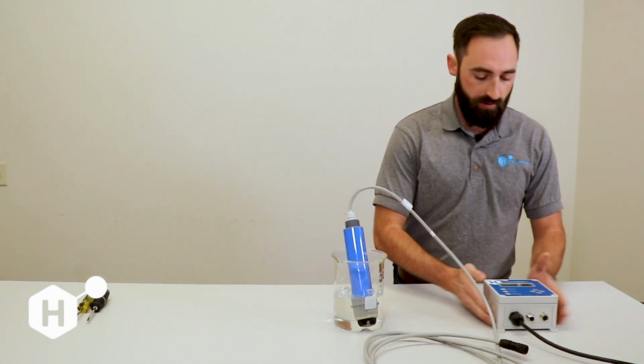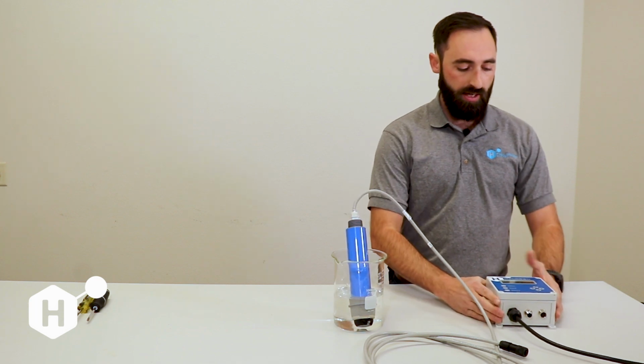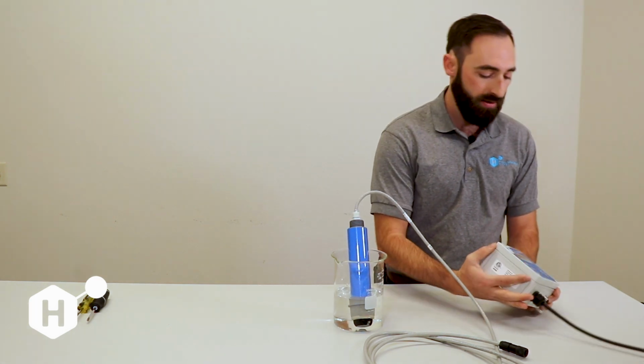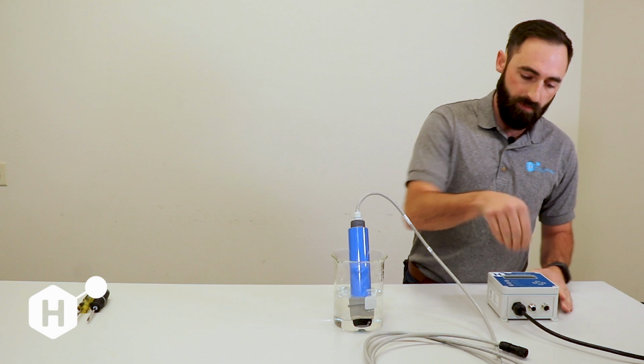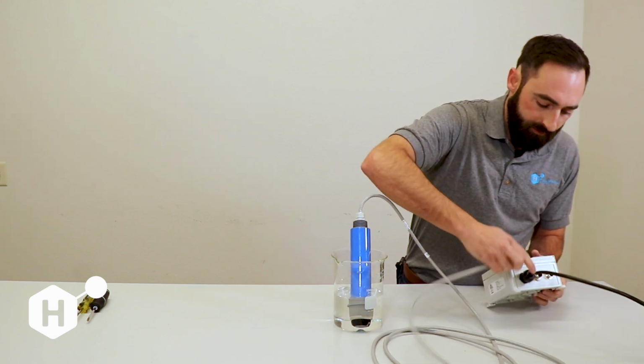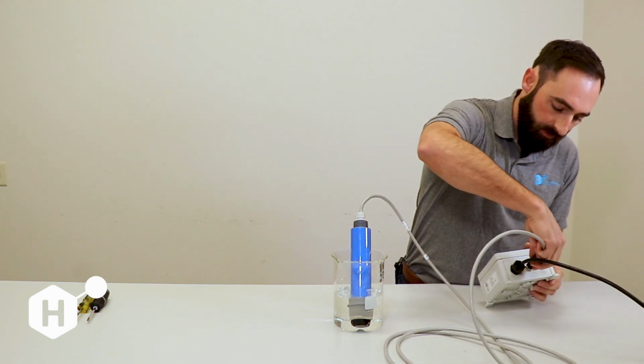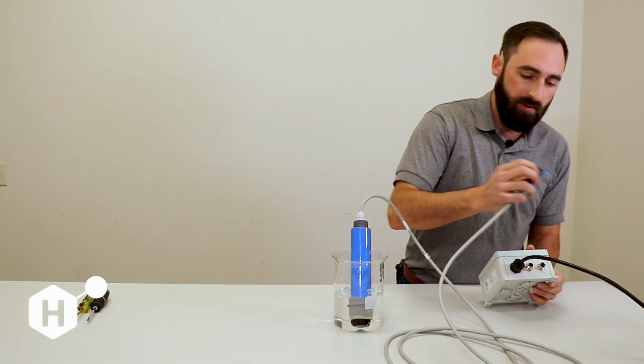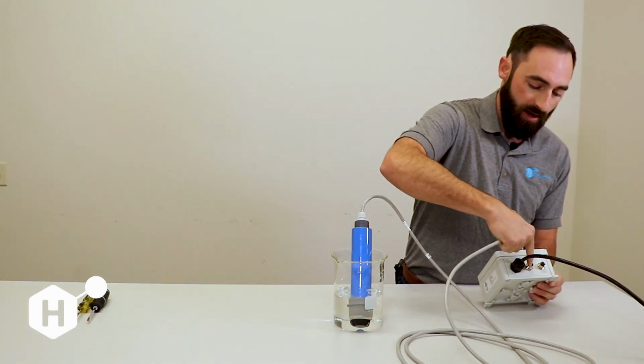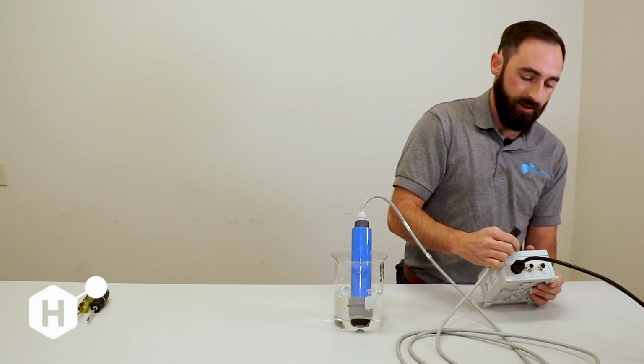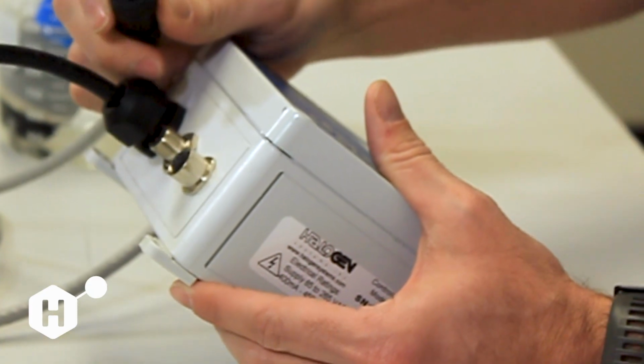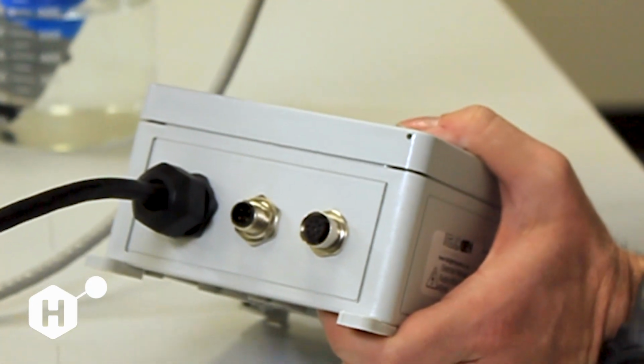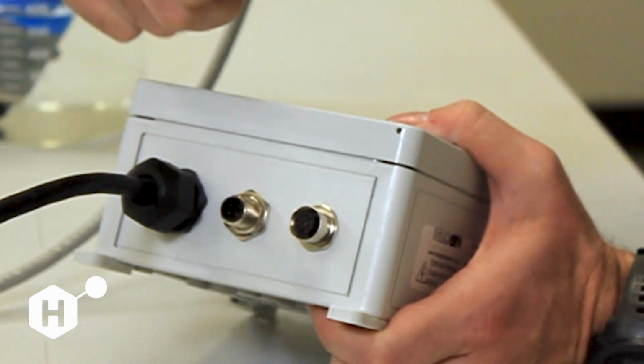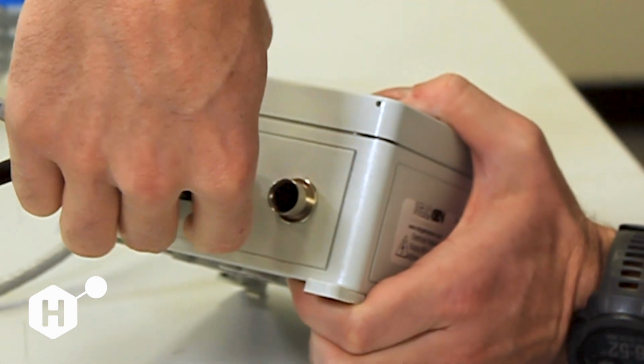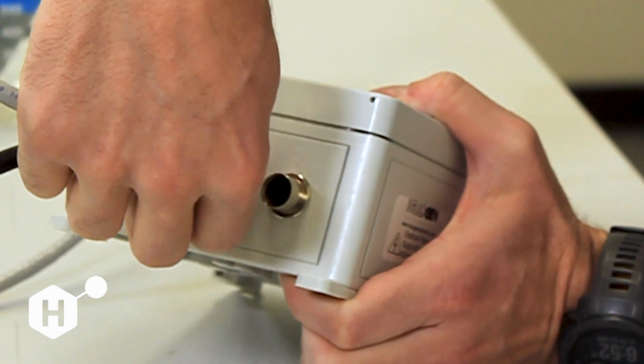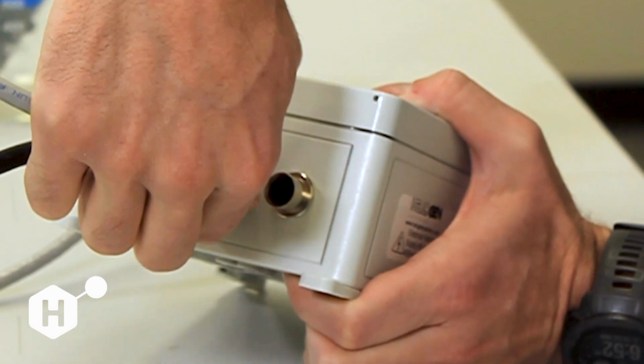The first thing you're going to do during the startup is, whether you have power to your display or not, go ahead and plug in the sensor. All of our M12 connectors have a notch at the back of the display. If you're using one of our municipal controllers, you'll be able to line the notch here up with the notch here, give it a little shimmy, and it'll drop in, and then go ahead and tighten. You'll know you have a good connection when you can hear the sensor start up.